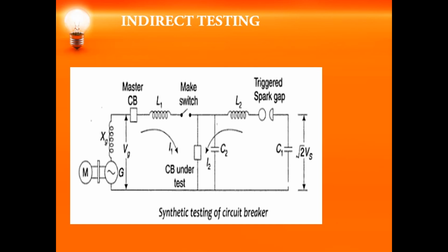So when we have a high voltage circuit breaker of large capacity to be tested, it is not possible in a laboratory setup to test with a very large power. In such a case, we go for indirect testing of the circuit breakers. Indirect testing is mainly of two types: the first one is unit testing, and the second one is synthetic testing. Unit testing: let us say you have a high voltage circuit breaker, it will have several arc interrupter units. Each unit has to be tested separately.